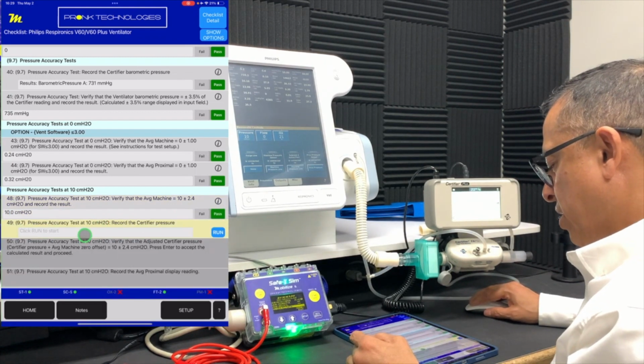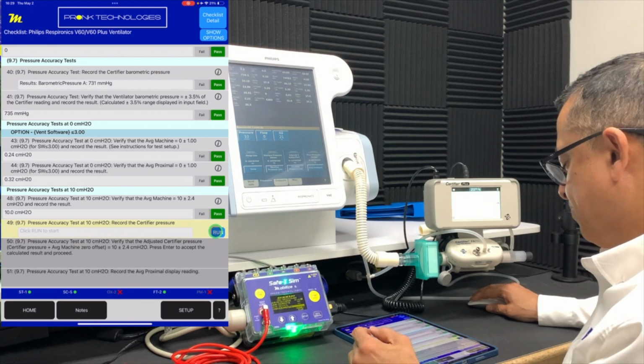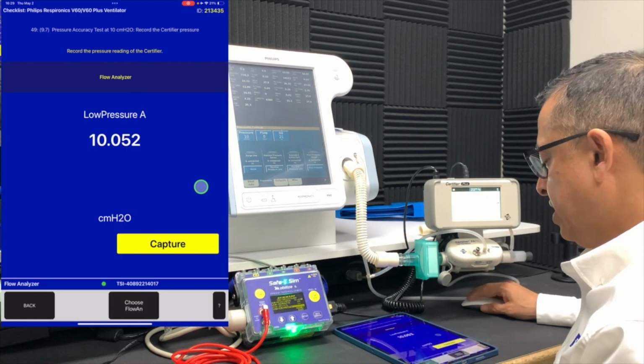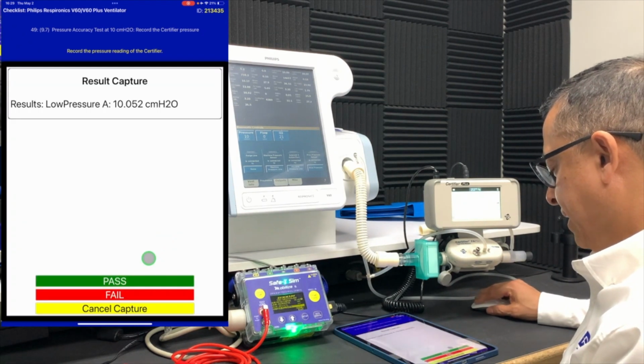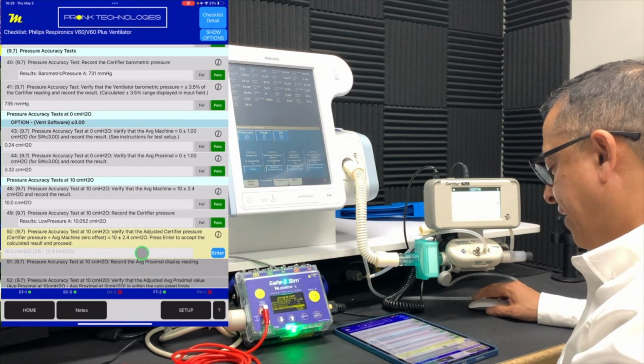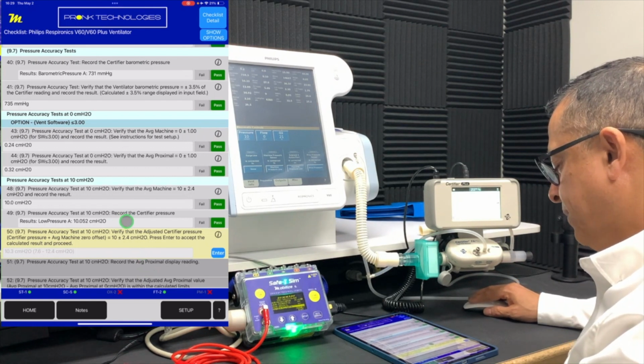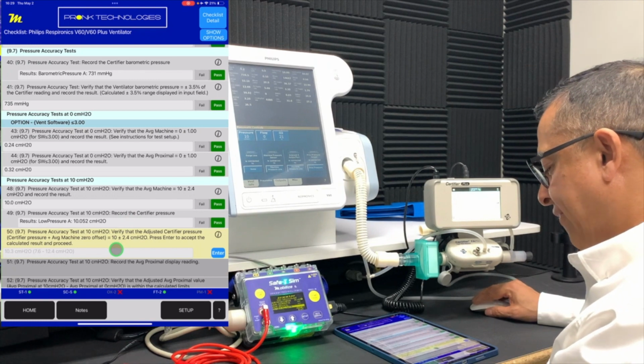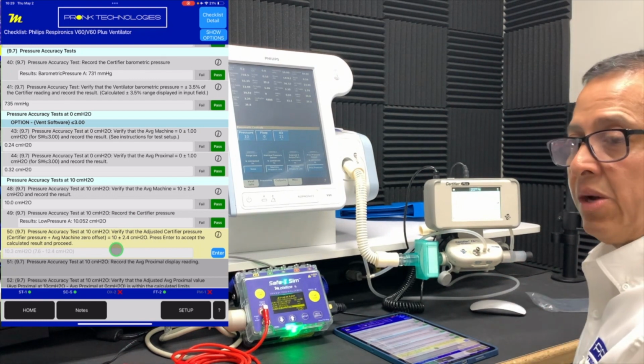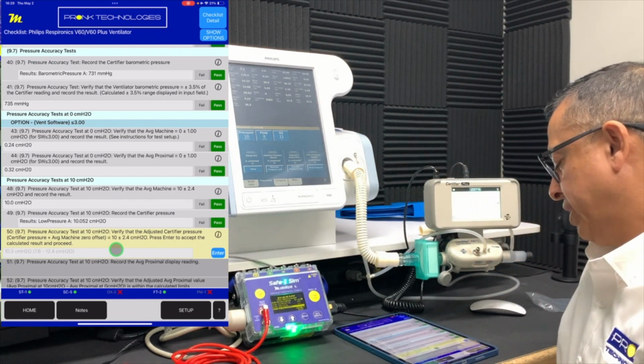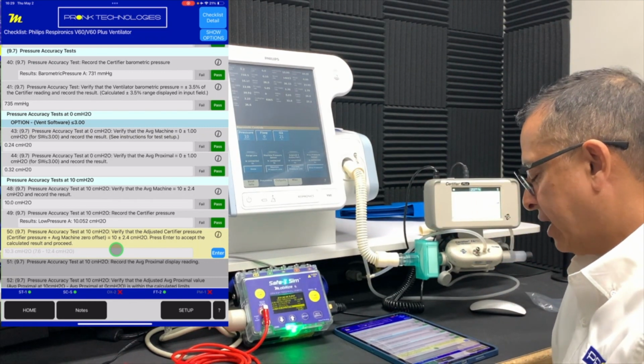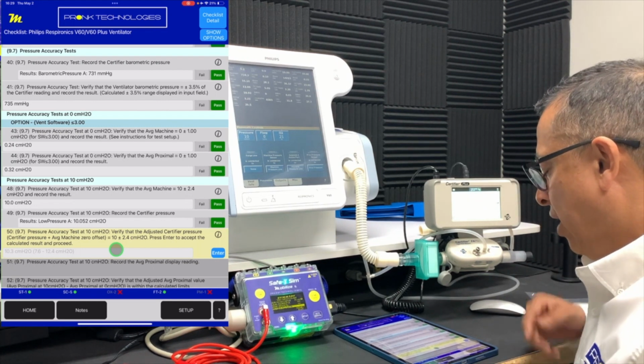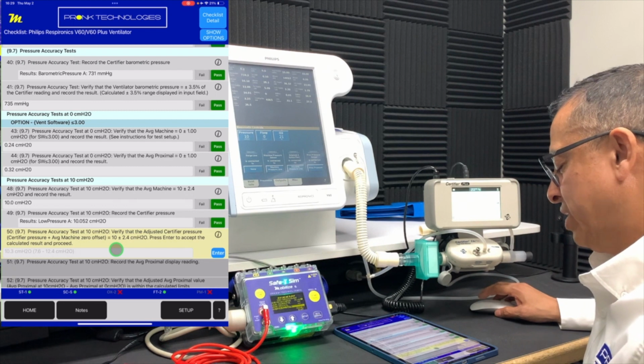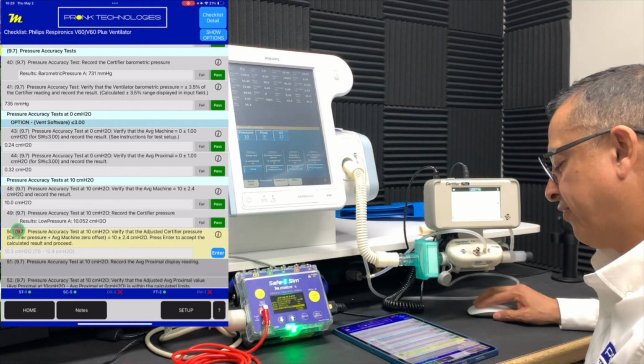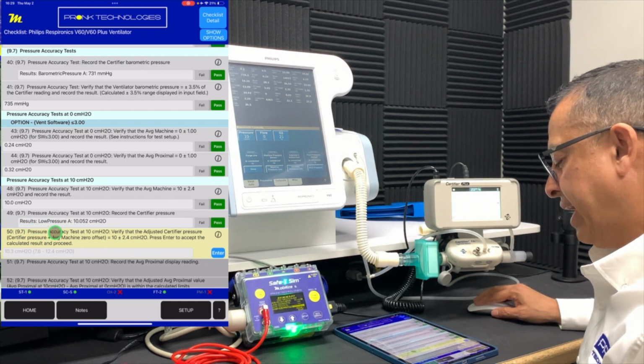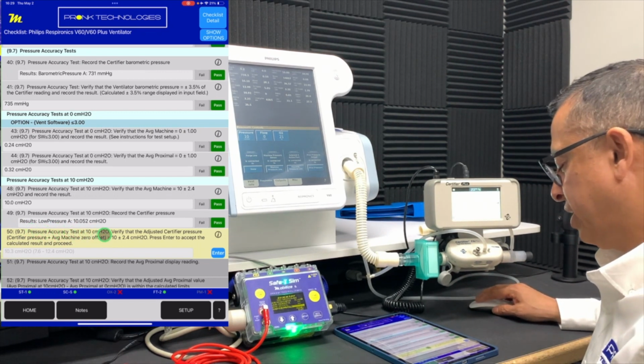The next one is verifying the certifier pressure. That of course matches what the pressure of the ventilator is, and you can see here's our measurement from the Certifier Plus. That is also good, and so we have that reference captured in the report as well. So now the following step involves something that's somewhat unique to this particular ventilator, which is doing a calculation. And the app, our intelligent checklist that we've created, allows these calculations to be automatically done. In this step, it involves confirming the certifier pressure plus the average machine zero offset needs to be within a particular range.